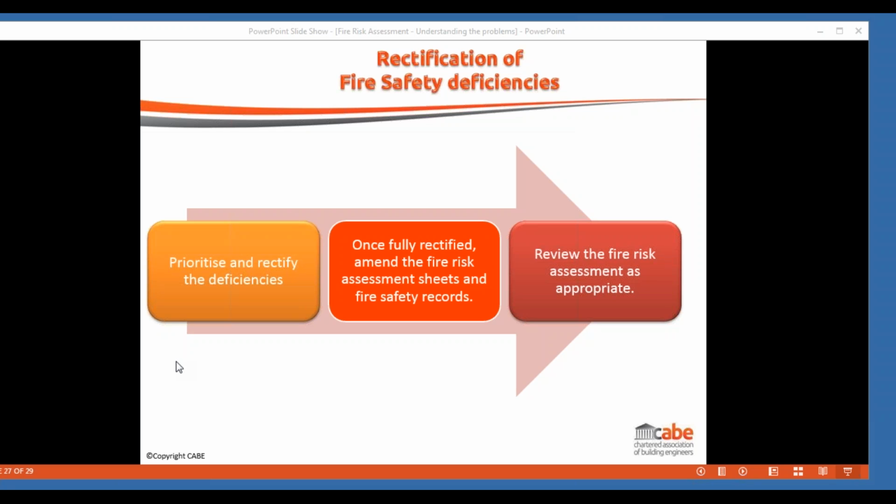The fundamental difference is that something that may be, if you like, sheltered housing or retirement type accommodation can be very akin to flats, in which case the risk assessment may only look at the procedures for the common areas. The difficulty is if it becomes semi-care home where some of the people in the flats or the accommodation need additional support and care, or it's in that transition stage, then yes, you would be looking at what's going on in the individual units of accommodation. So it doesn't necessarily matter what label's on it. What you have to look at is the circumstances that are presented to you and how it's really being used and managed.